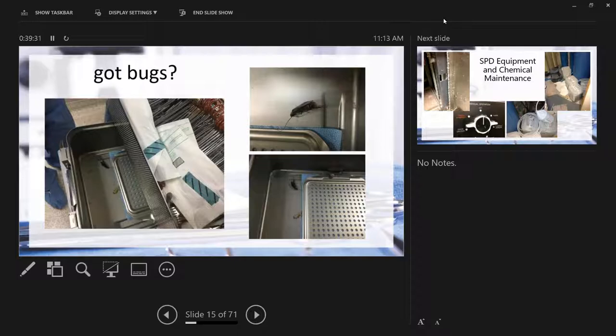We found the bug, and what happens is we don't maintain our pans. People think they're indestructible when they're not. They're just like anything else that you didn't maintain. So the seal around the top was not good, and the cricket crawled up inside. We sterilized it, and he met his demise. But if the technician hadn't caught it, we would have used it on the patient.